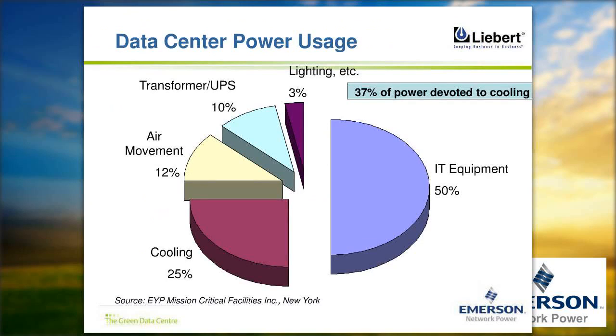Now, if you look at the demography of data center power consumption, when you are feeding 100 kilowatt of power into a data center, only 50% of that power is available for IT. And that's where we say PUE is 100 upon 50. The IT load is the pure useful power. Our endeavor should be, with the same facility kilowatt, how much I can increase the percentage of IT. Can I increase it to 60? Can I increase it to 75? That's how we can reduce this ratio, and that's how it will help us improve the overall energy efficiency of the data center.